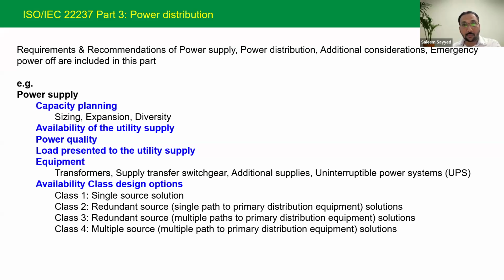If two different substations are not possible, then at least two different transformers from the same substation. That is one of the major aspects of getting the utility supply to your premises. Diverse route of that supply: either it will be from underground cables or from overhead lines. You have to make sure these lines follow a redundant path, so any mechanical failure should not hamper both sources. That is the main objective of giving a diverse path.